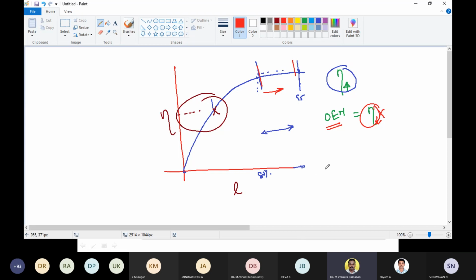If the motor nameplate information isn't available, at least the rating, the HP of the motor, has to be available. Then we have to do the energy analysis and see how much power it draws. Only then will we be able to tell whether the motor is overloaded or not. Only when overloading or underloading is present do we go for an efficiency study. If the loading is appropriate, then the majority of motors would be operating effectively and efficiently.